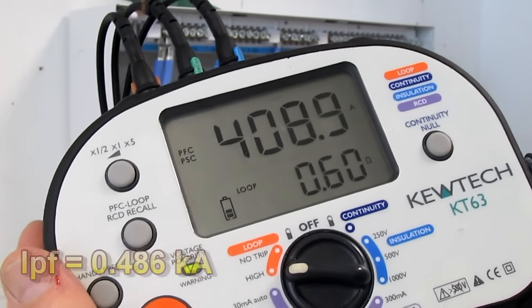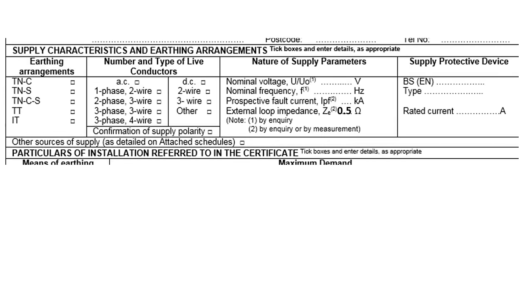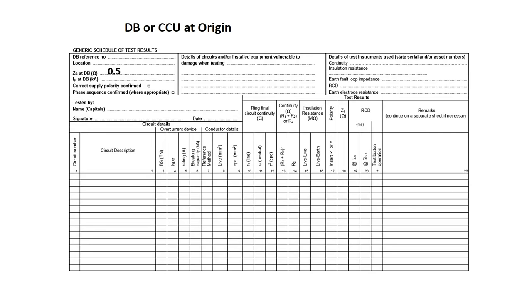Our IPF — our prospective fault current — is quite simply the highest of these two values. The value of IPF can now be written on our electrical installation certificate under the supply characteristics and earthing arrangements, in the box showing IPF in kiloamps. So I'm going to round up our IPF of 0.486 to 0.49 and put it in the box. This value can also be written on the top left-hand side of our schedule of test results just underneath where we'd written our ZS at dB reading of 0.5, so let's put in 0.49 and also tick the supply polarity box.